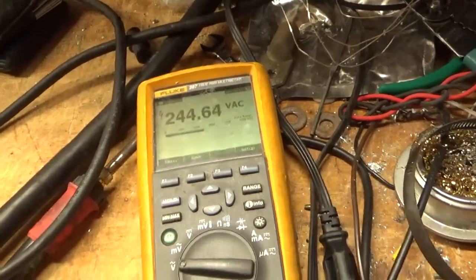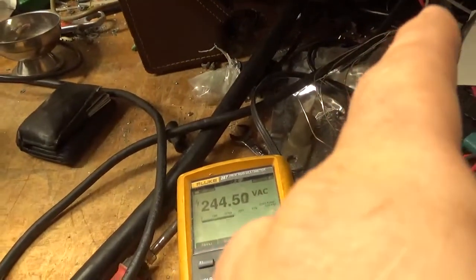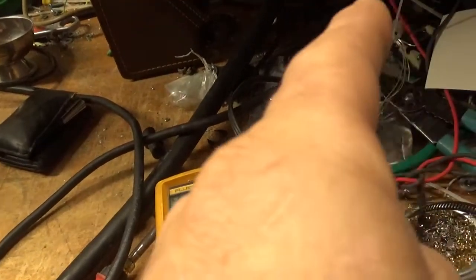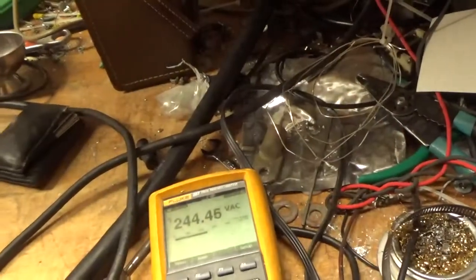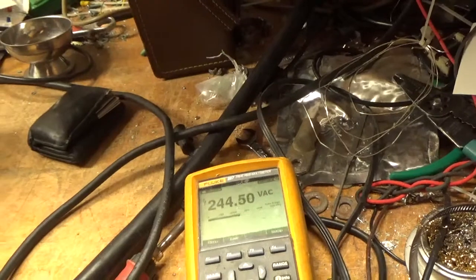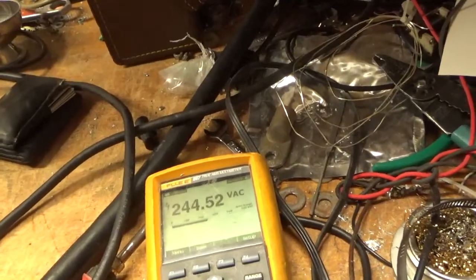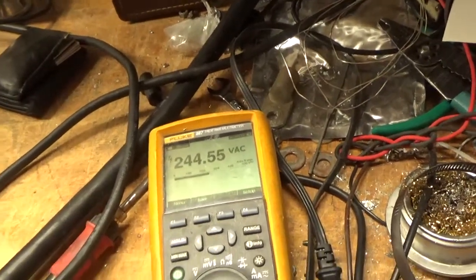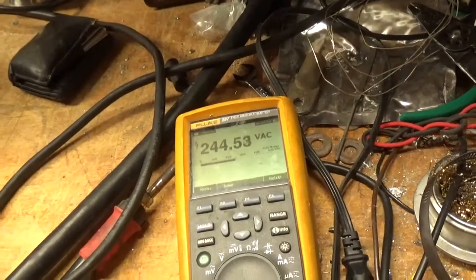So this time we have it across. We have the current meter reading one leg of the 240, but we're not isolating the primary of the transformer from everything else this time. So we'll have an extra amp or so, for the blower and other things, supplies that run the relays.